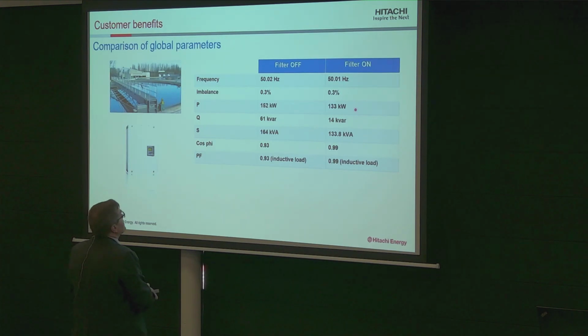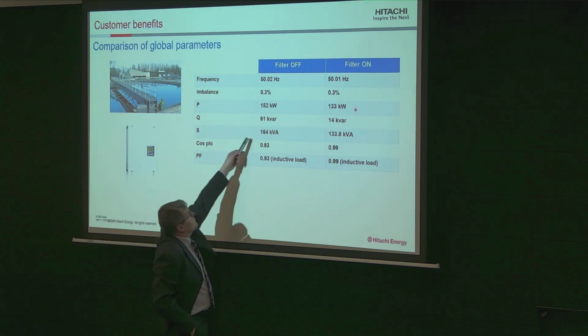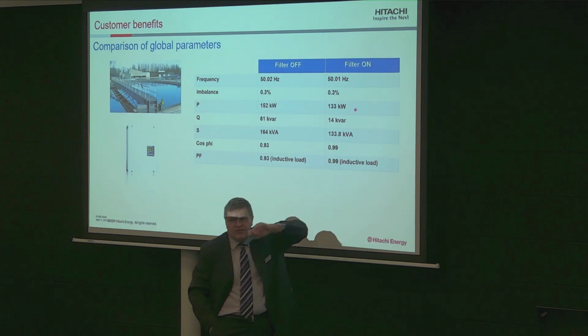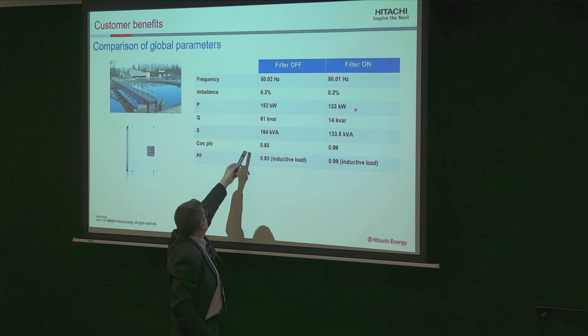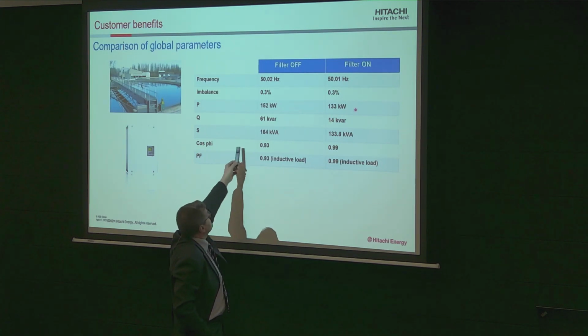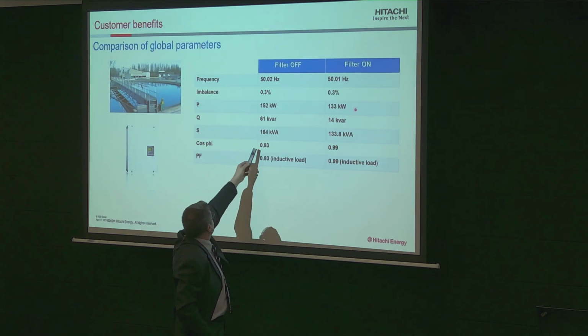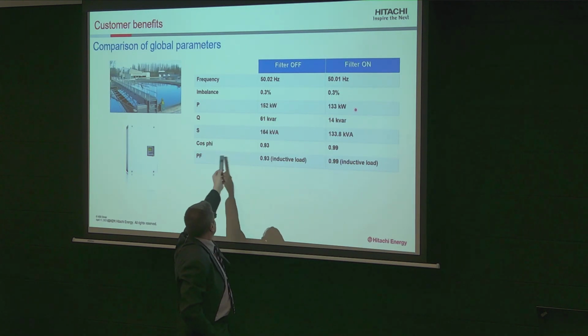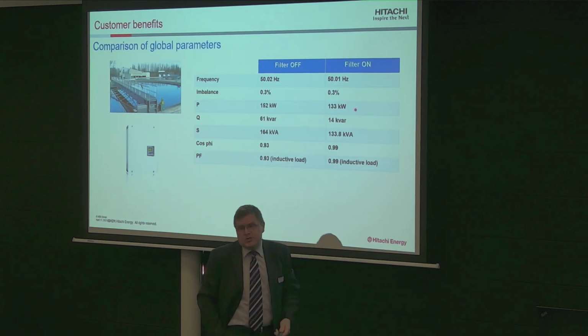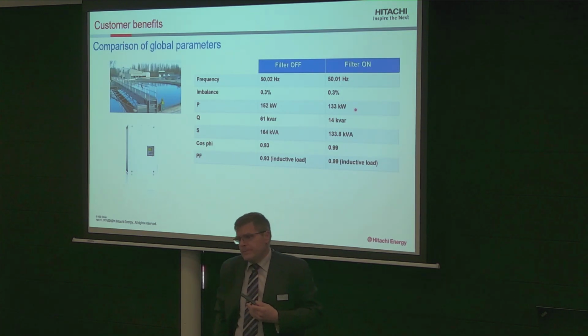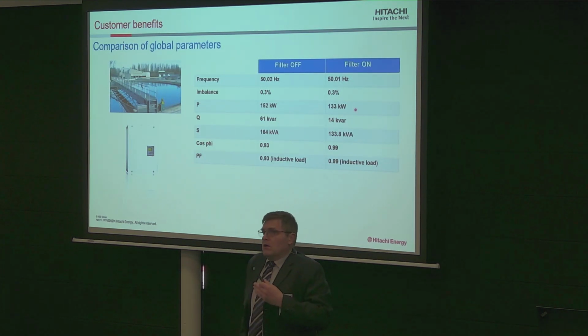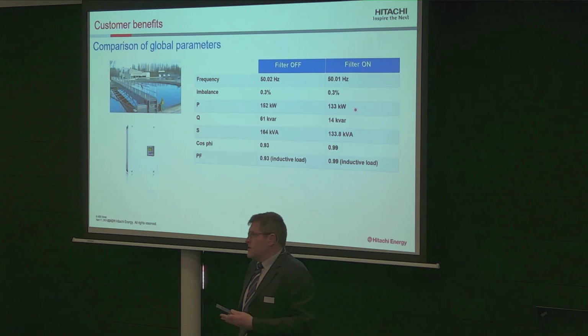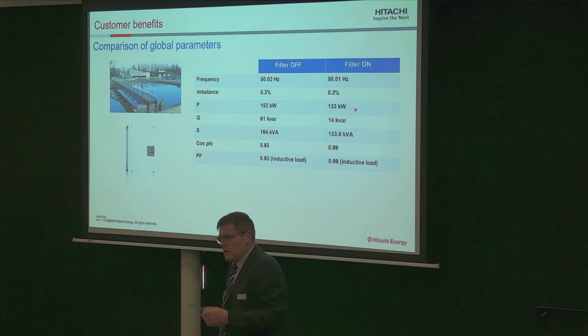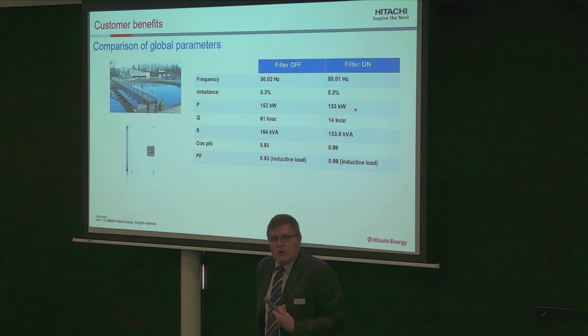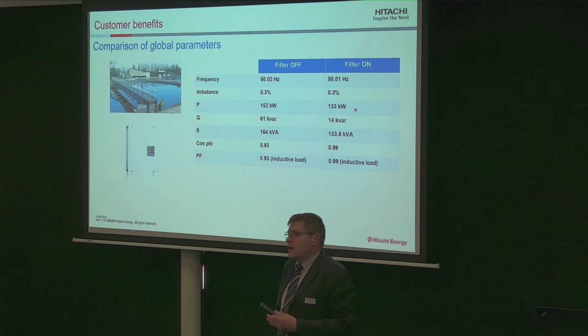Alors, I also take this example because here, that's important. You have here the apparent power before and after, and you see that the cosinus phi normally is not changing, but the power factor changes. In many applications today, we have a capacitor bank which is specified by default because it's a well-known topic. But a variable speed drive today doesn't require any power factor correction because the cosinus phi is already good.